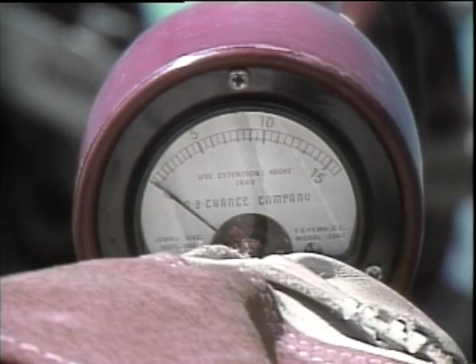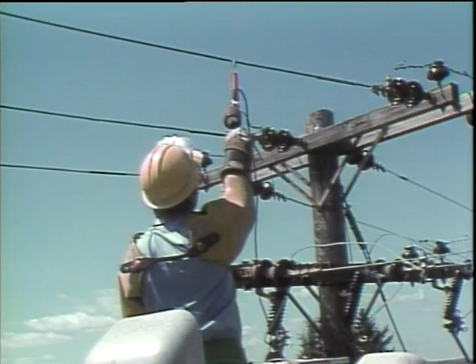The phase to ground test is repeated for the other two lines on the circuit. It's important to test all the lines on the de-energized circuit you'll be working on. After the circuit has been tested, recheck the tester to be sure that it works and your results are accurate.